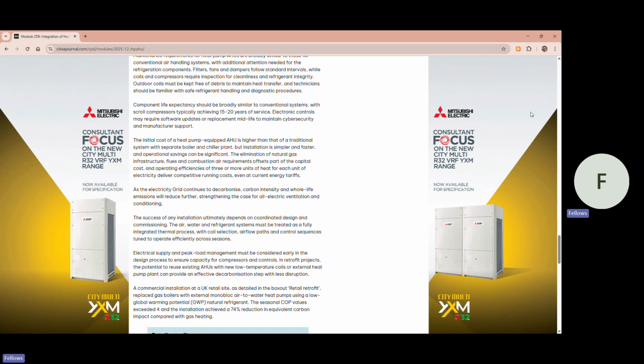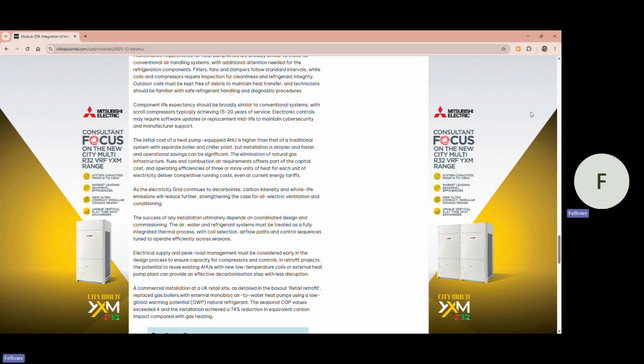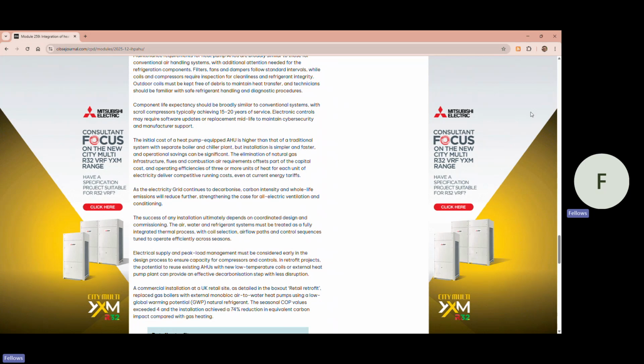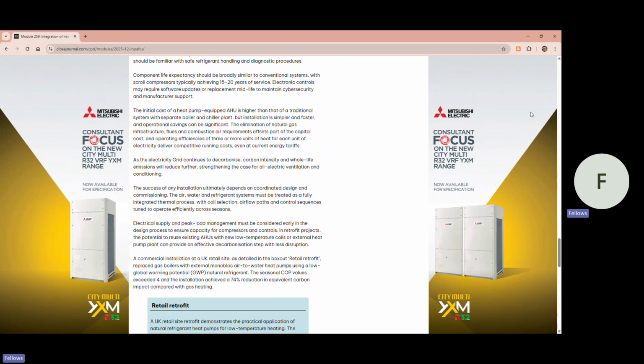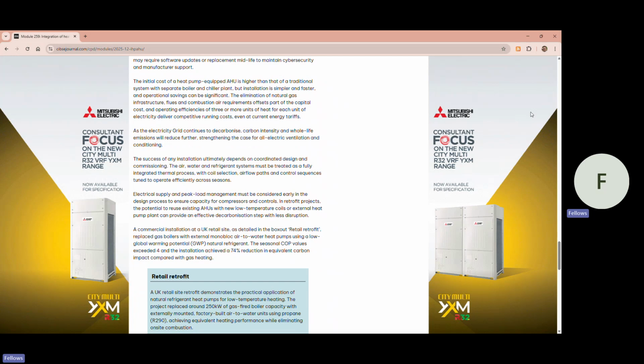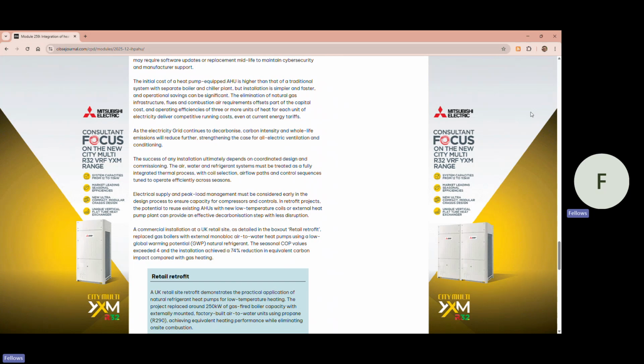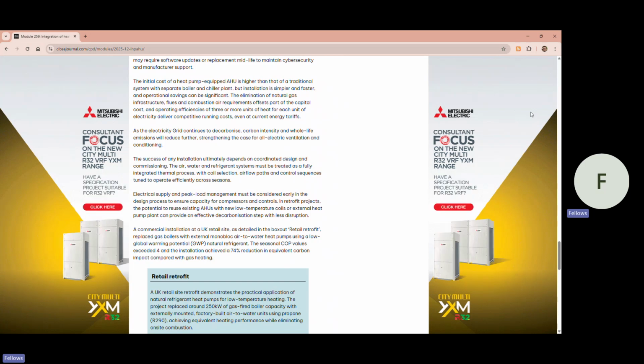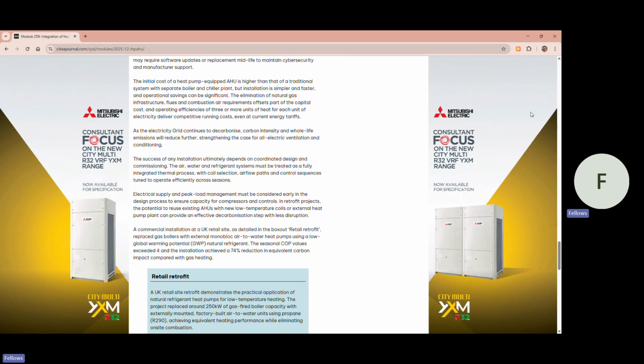As the electricity grid continues to decarbonise, carbon intensity and whole life emissions will reduce further, strengthening the case for all electric ventilation and conditioning. The success of any installation ultimately depends on coordinated design and commissioning. The air, water, and refrigerant systems must be treated as a fully integrated thermal process, with coil selection, airflow paths, and control sequences tuned to operate efficiently across seasons.